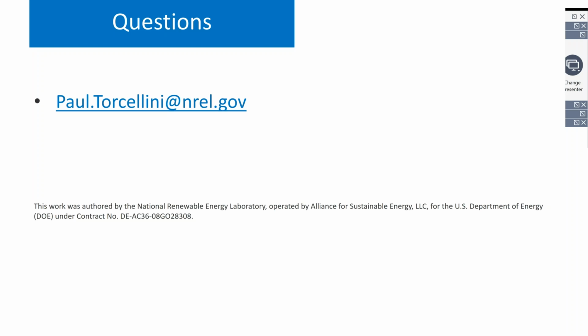Think of it like this: a school is running, maybe the air conditioning is on, it's a sunny hot day, the PV panels are cranking out power, and a little cloud comes over for 15 minutes. That knocks out the PV system and the daylighting system, so the lights come on while the PV is basically shut off, and the air conditioning is still running. You'll hit the same peak demand charge as if you didn't have the renewable energy system at all.